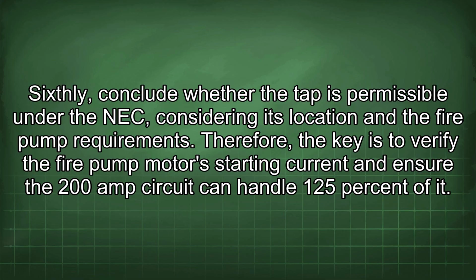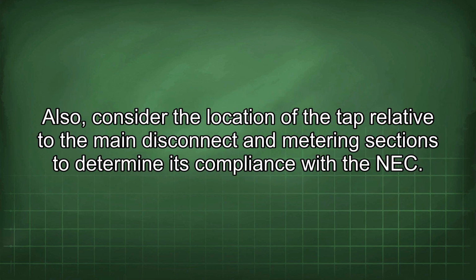Therefore, the key is to verify the fire pump motor's starting current and ensure the 200 amp circuit can handle 125% of it. Also consider the location of the tap relative to the main disconnect and metering sections to determine its compliance with the NEC.